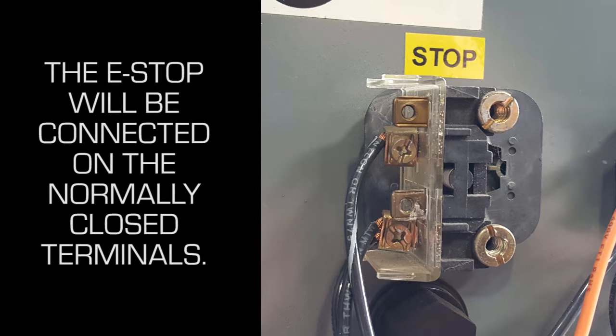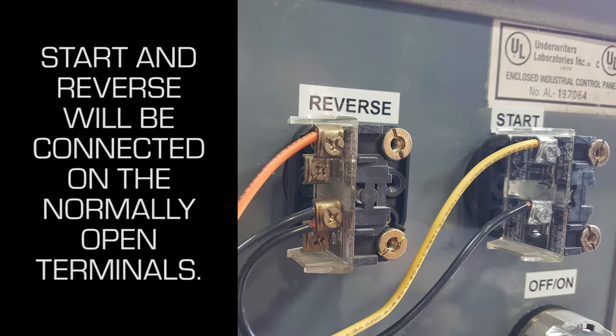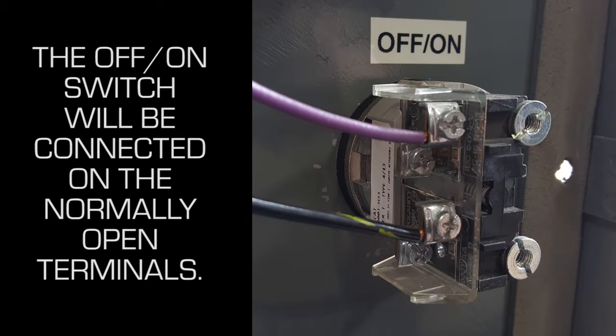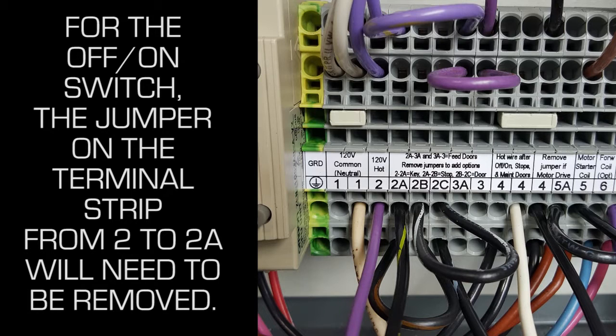The e-stop will be connected on the normally closed terminals. Start and reverse will be connected on the normally open terminals. The off-on switch will be connected on the normally open terminals. For the off-on switch, the jumper on the terminal strip from 2 to 2A will need to be removed.